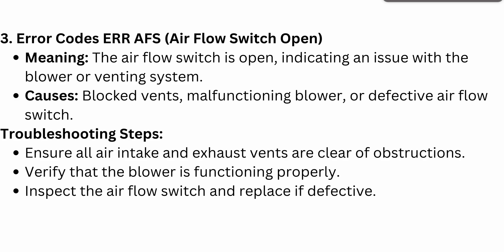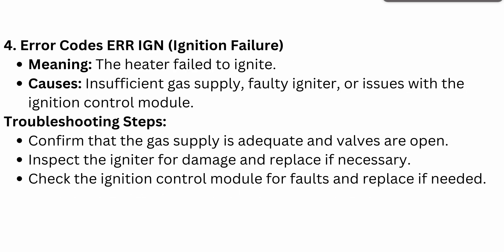The fourth error code is ERR IGN — ignition failure. It means the heater failed to ignite. Causes can include insufficient gas supply, a faulty igniter that is not working properly, or issues with the ignition control module. To troubleshoot, confirm that the gas supply is adequate and valves are open, inspect the igniter for damage and replace if necessary, and check the ignition control module for faults and replace if needed.